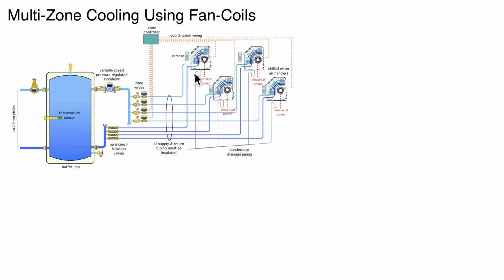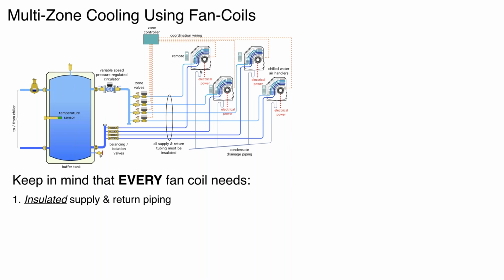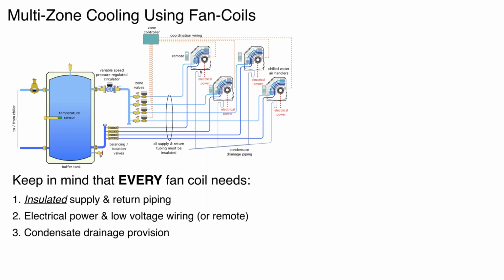You also need condensate drainage, and you need line voltage to power the blower. So you can see what I'll call the infrastructure needed to each of these fan coil units is substantial. So again, insulated supply and return piping, line voltage and low voltage wiring, condensate drainage, a zone valve, okay?